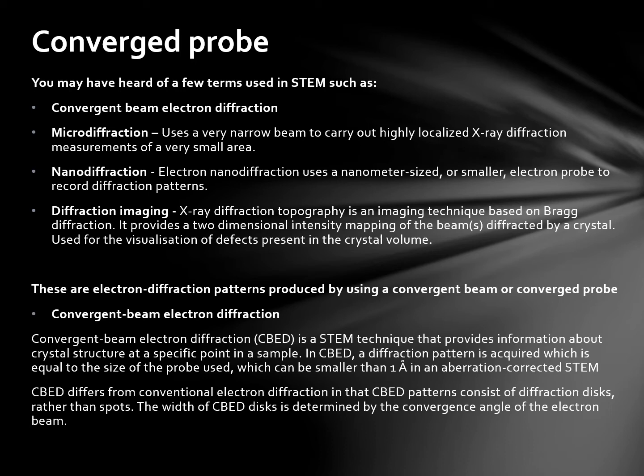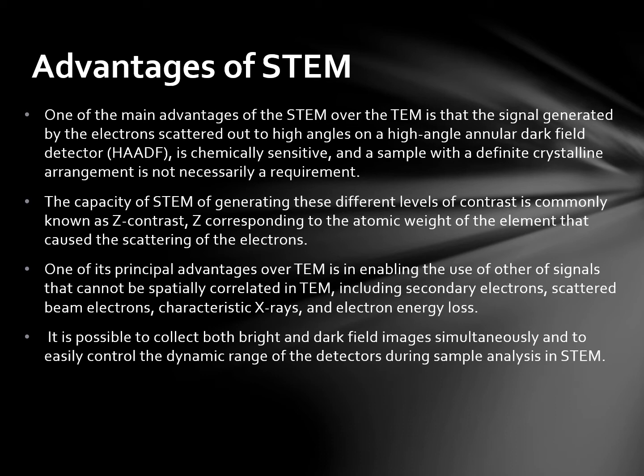One of the main advantages of the STEM over the TEM is that the signal generated by electrons scattered out to a high angle on a high angle annular dark field detector is chemically sensitive, and a sample with a definite crystalline arrangement is not necessarily a requirement. The capacity of a STEM to generate these different levels of contrast is commonly known as Z-contrast, Z corresponding to the atomic weight of the element that caused the scattering of the electrons. STEM also enables the use of other signals that cannot be spatially correlated in TEM, including secondary electrons, backscattered electrons, characteristic X-rays, and electron energy loss. It is possible to collect both bright field and dark field simultaneously and easily control the dynamic range of detectors during analysis.